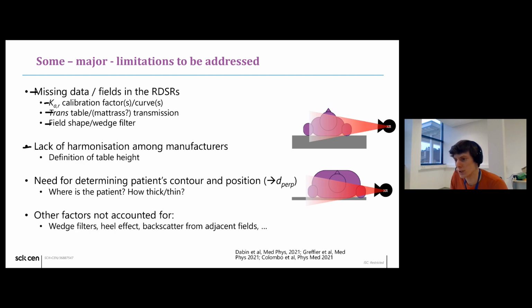There's also a lack of harmonization among the manufacturers. The way the table height is defined in the RDSR is different if you are looking at Siemens and GE or if you're looking at Canon and Philips. It might seem a detail, but it can have an important effect on the skin dose. And also, maybe the most surprising of all, there is no way for the current systems to know the patient contour, the patient shape, and the patient position on the table. And you have here a very simplistic representation. For a skin dose mapping system, there is no way to know if the patient is well centered on the table or if the patient is very close to the X-ray beam. And of course, it will have a very big effect on the dose at the patient's skin.